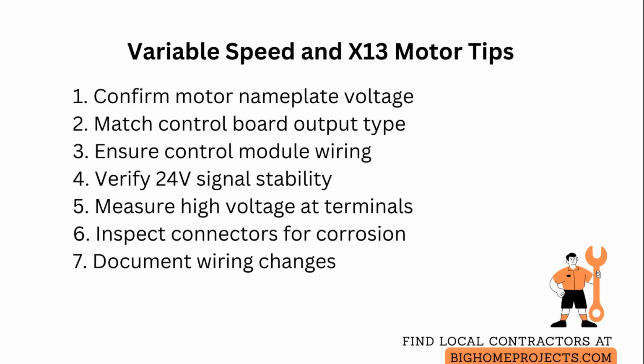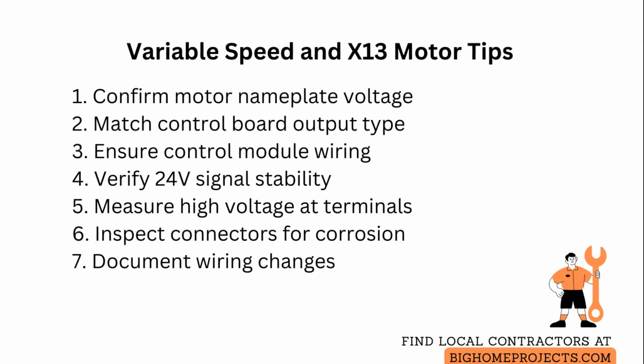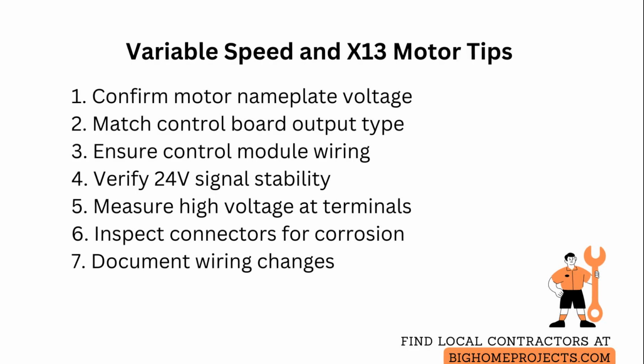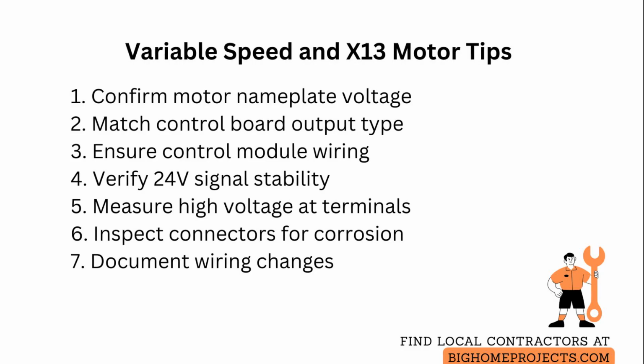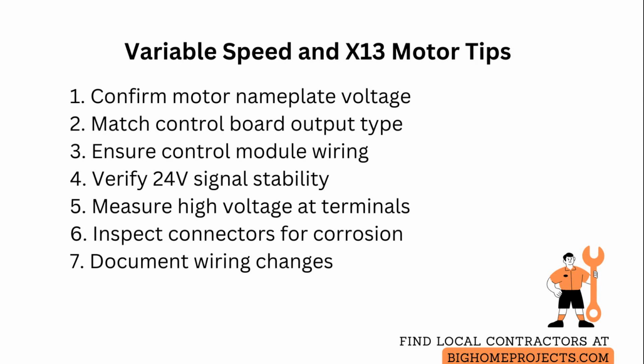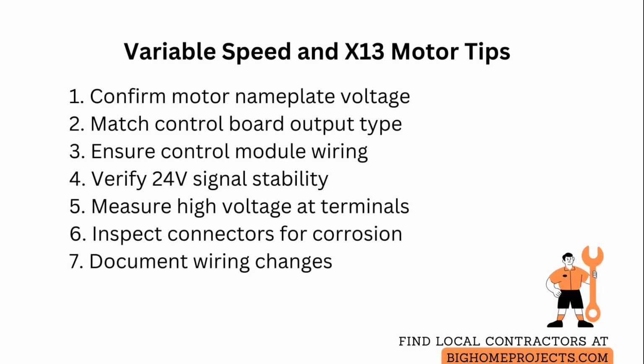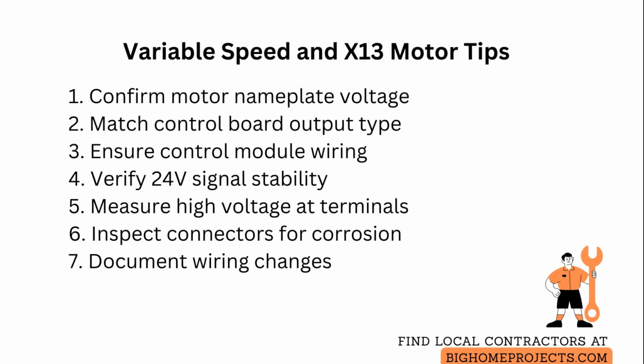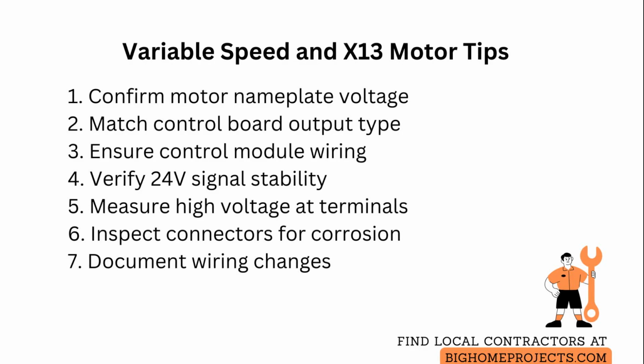for fan operation. When replacing components, match the motor part number, control interface type, and venting or mounting characteristics to avoid compatibility problems, and if the motor uses an external module, inspect connectors and harnesses for corrosion and correct pin mapping. For installers, document wiring changes and label control conductors explicitly. And for technicians, use manufacturer service manuals to interpret status codes and to follow recommended start ramp profiles so the control board does not falsely flag a motor fault. Remember that a stable low-voltage control signal and intact control electronics are just as critical as confirmed high-voltage presence for these motor types to run reliably.